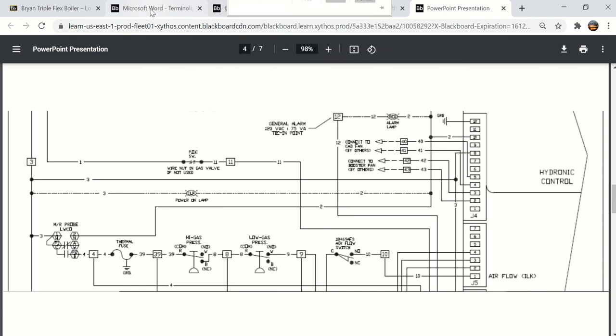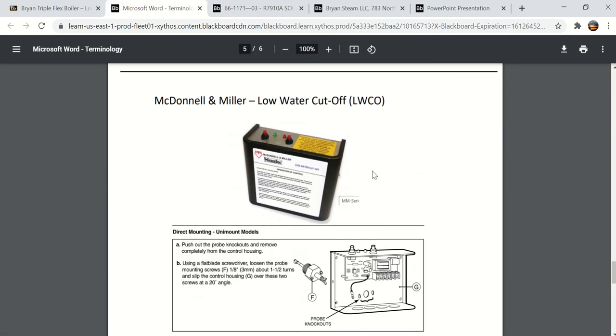So if we go to the terminology page and you scroll down here, you'll see McDonnell-Miller low water cutoff. This is a picture of it. It has a test and reset button. It has indicator lights for when power's on, and a red indicator if it's tripped or it's not seeing water. You look down here. Here is the probe. The probe has a ceramic cover. It's a brass nut, and what that probe is looking for is conductivity to ground. So it's looking for water to create a conductive path to ground so that it knows there is water present, and that's what a probe type low water cutoff looks for.